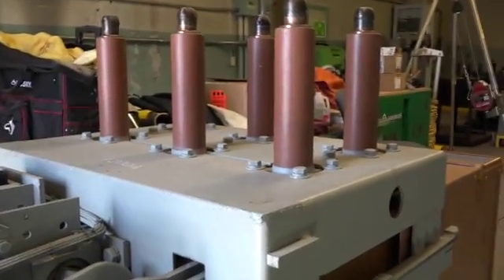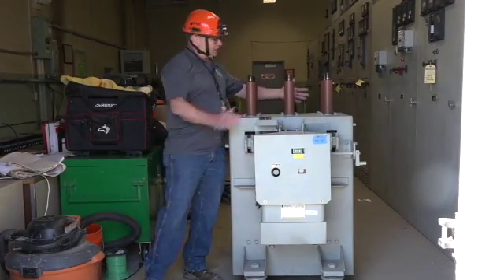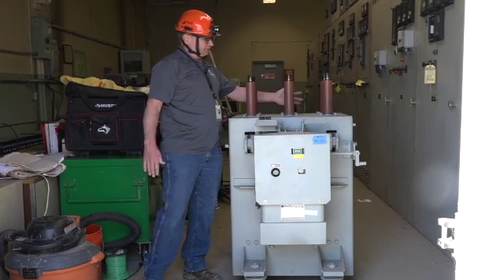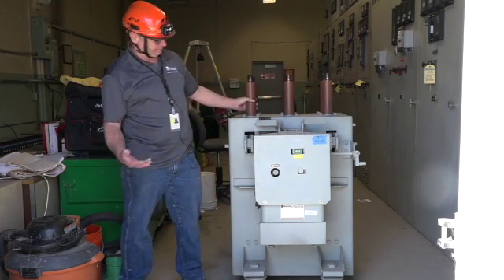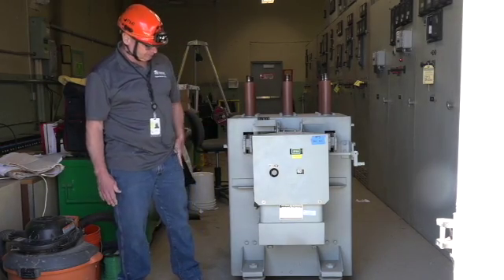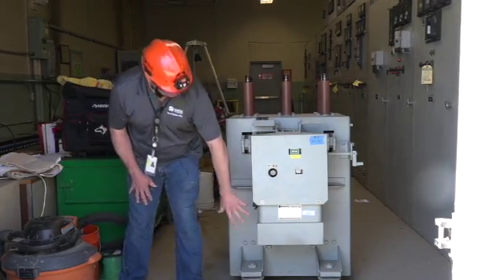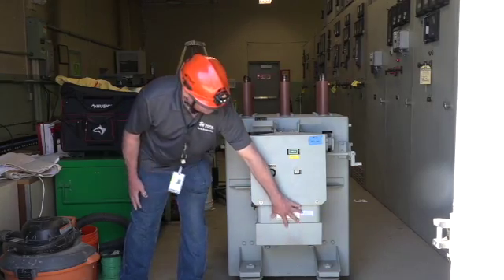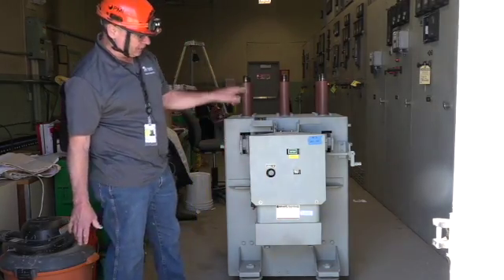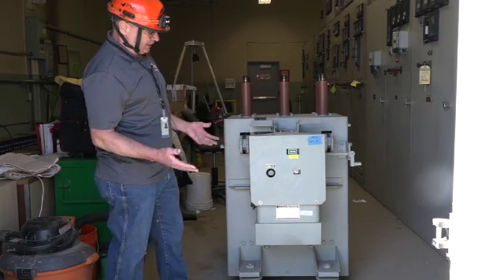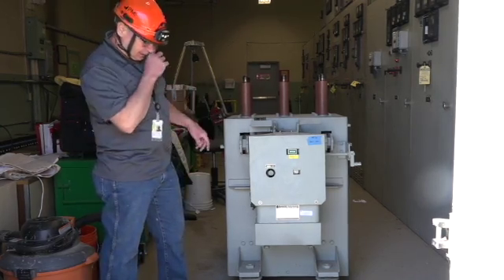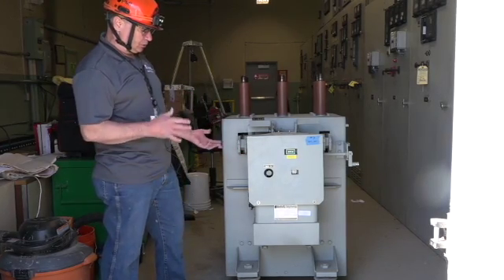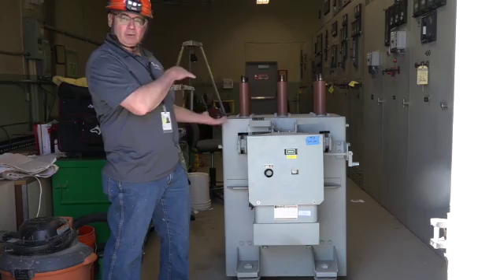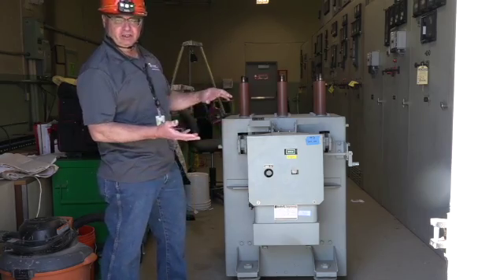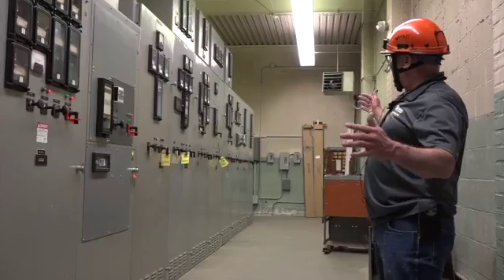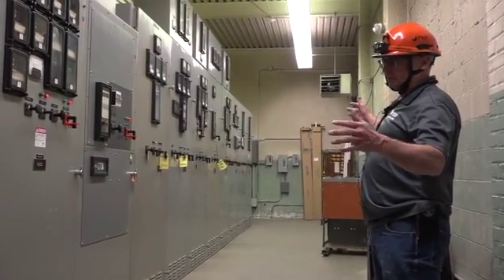There's the line, which is on the front, and the load side is the back, if it's a load breaker. It's a large magnet, and that's what causes, with the 130 volts DC from the battery rack, the breaker to close. And then it's all spring loaded, so when it opens, the springs quickly open it so it extinguishes the arc quickly.